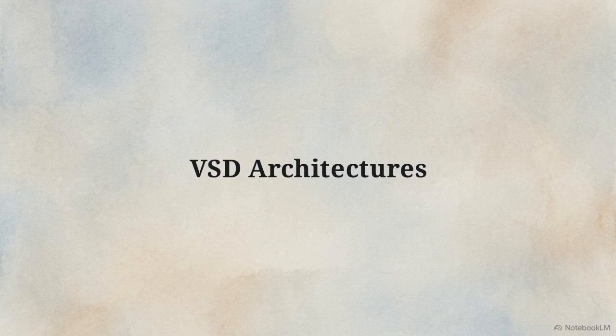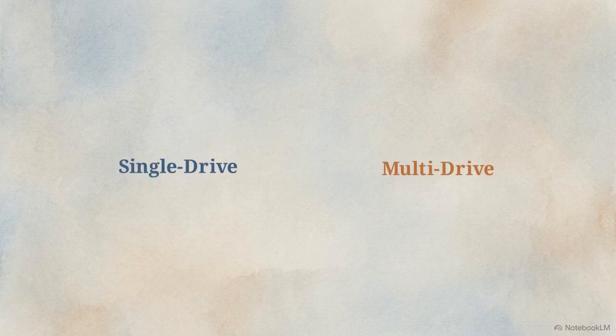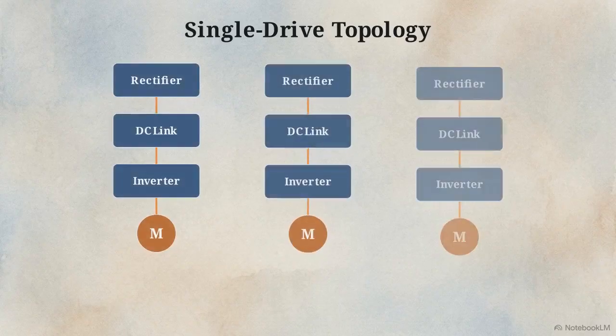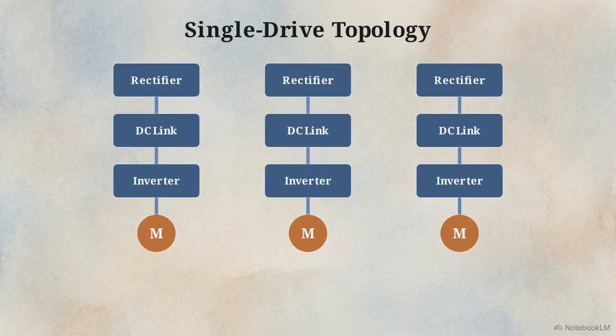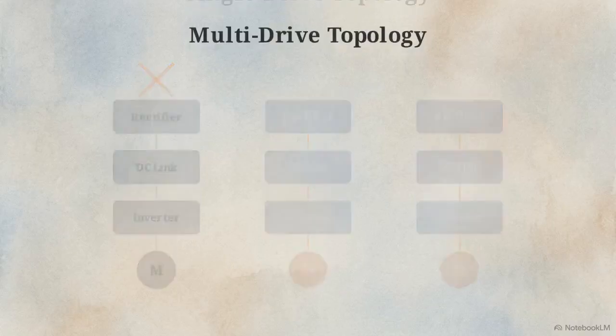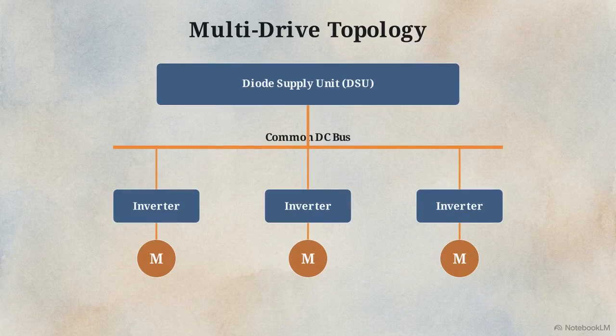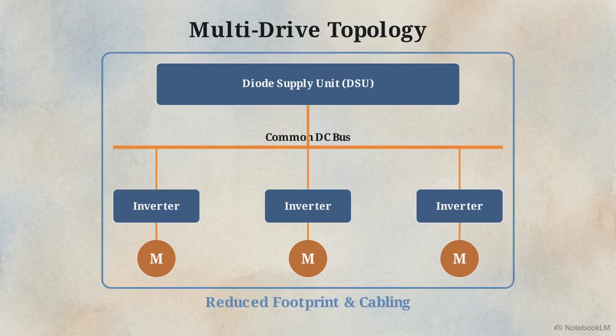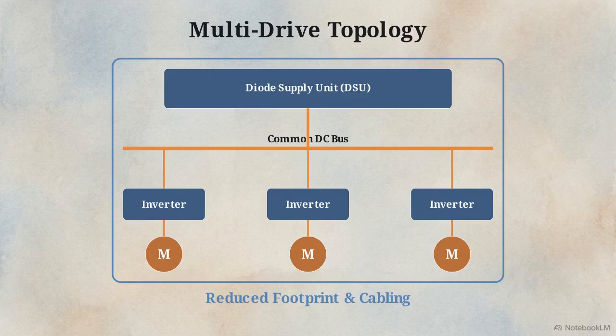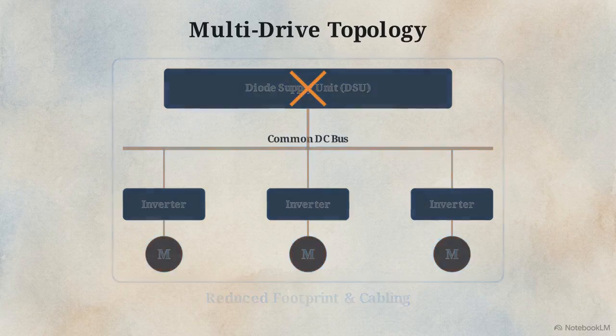Beyond the individual motor, engineers must arrange these drives into a larger architecture, choosing between single-drive and multi-drive topologies. In a single-drive topology, every motor has its own independent rectifier, DC link, and inverter. This prioritizes fault isolation. If one component fails, only that specific motor is affected. A multi-drive topology uses a shared approach. One massive rectifier and a common DC bus feed multiple independent inverters. This reduces footprint and cabling costs.